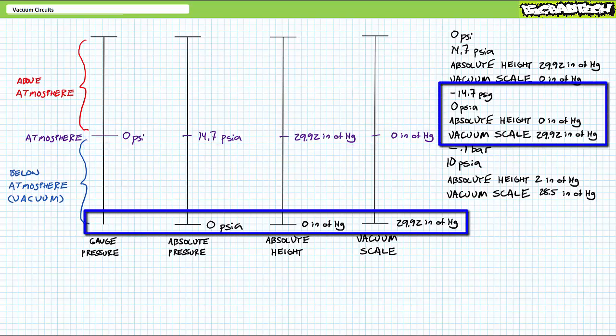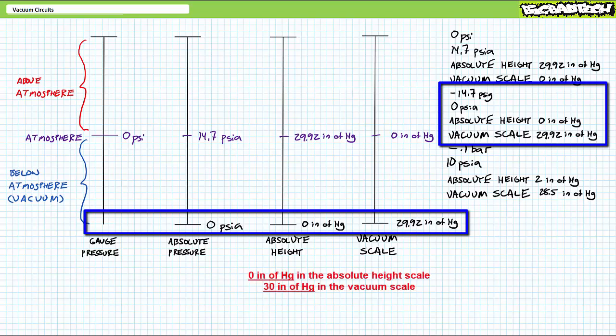The next four measurements all express the same perfect vacuum condition. Negative 14.7 PSI gauge, zero PSI absolute, zero inches of mercury in the absolute height scale, and 29.92 inches of mercury in the vacuum scale are all super strong perfect vacuums.